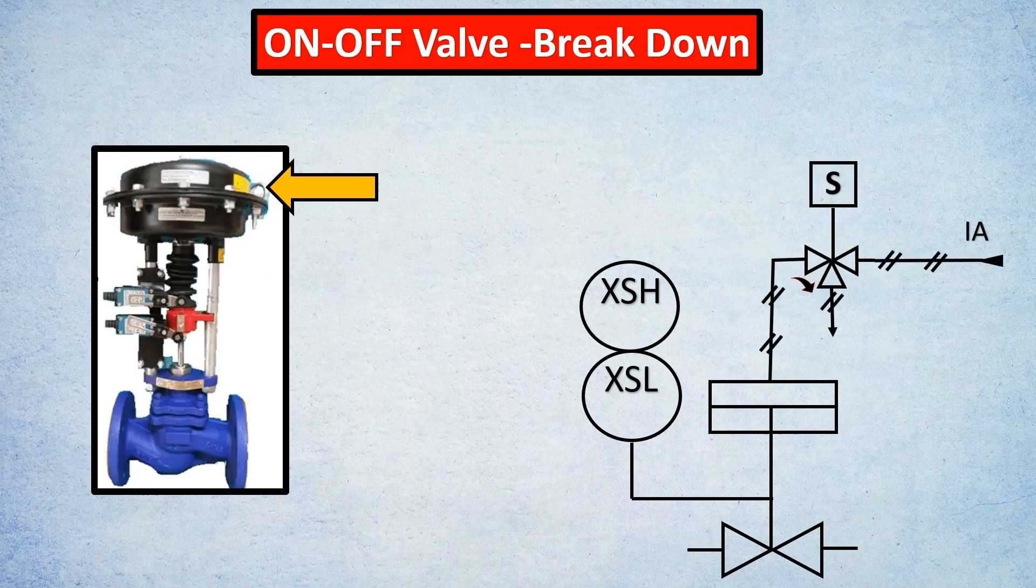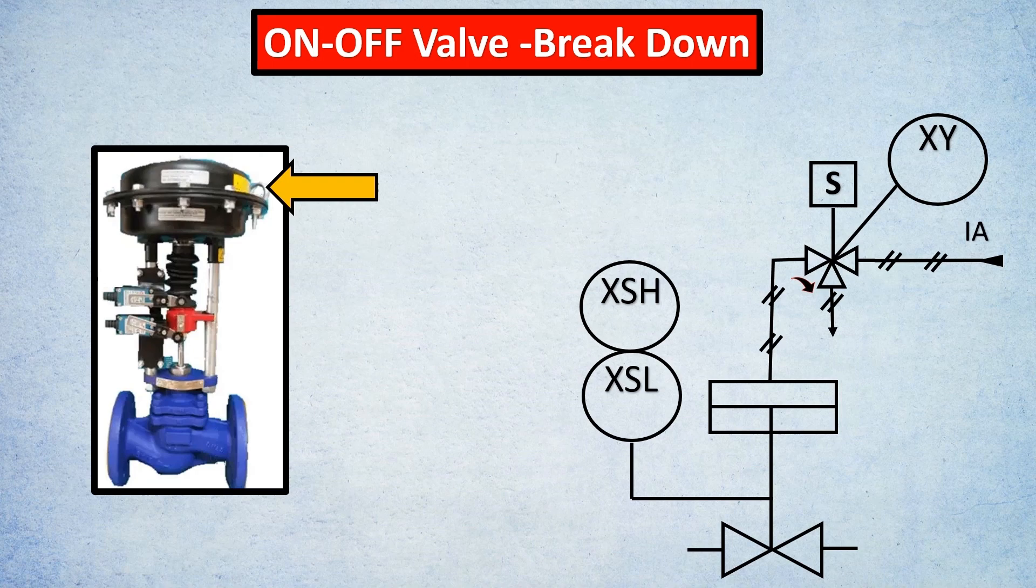You need an air supply for the valve to work. Here's our solenoid valve with the instrument air. Usually a solenoid valve has to be named, so we put XY there. For limit switches, it's usually XSH or XSL. The H stands for high and L stands for low. Sometimes it is open.